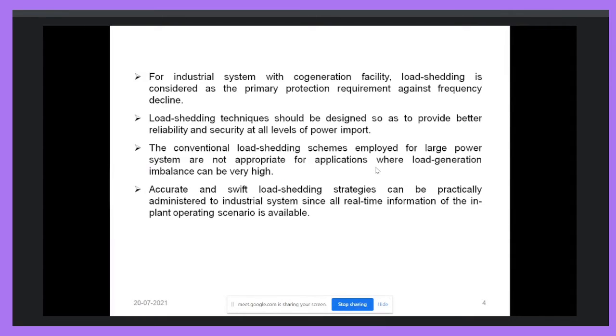If there is a large difference between generation and load, there will be a rapid frequency change. Suppose a greater amount of load is connected but there is less generation, then the frequency will decay very fast, and that can trip the frequency protection of the generator and reduce the output of the motors. Because we know that the speed of a motor, for example an induction motor, depends on frequency and the number of poles. So if frequency reduces, speed will reduce, and if speed reduces, the output of the motor will reduce.